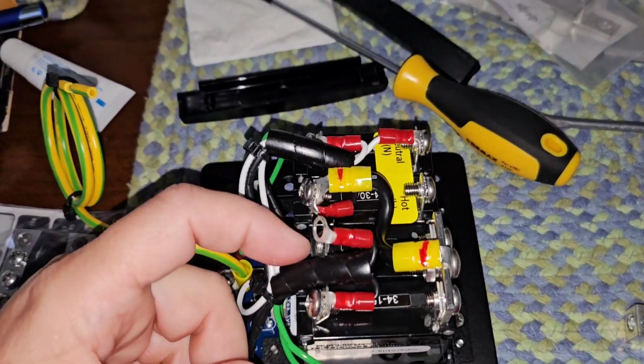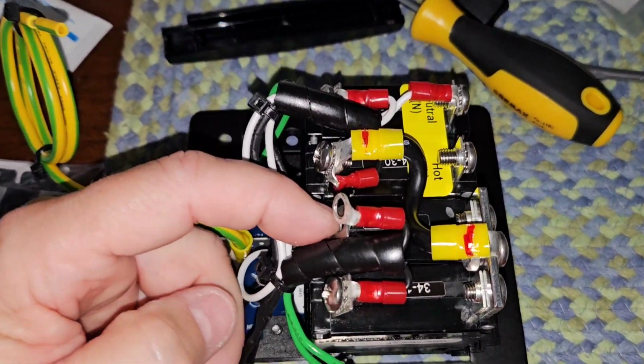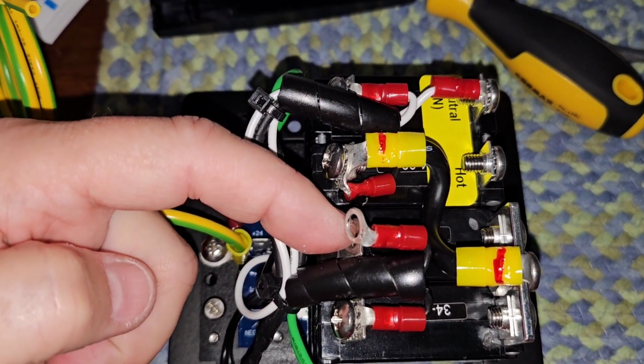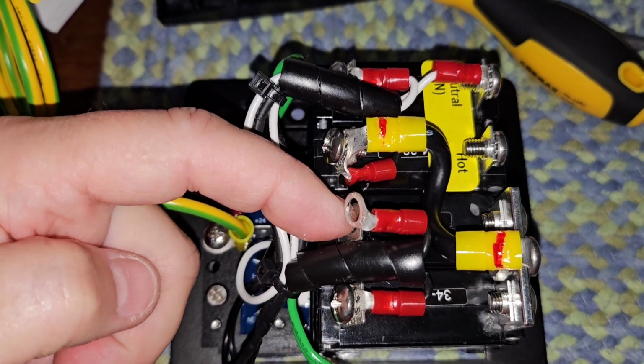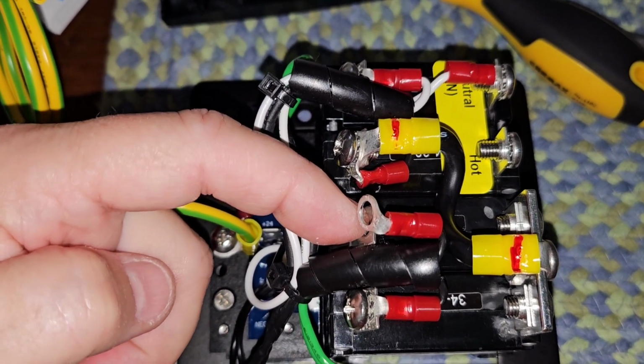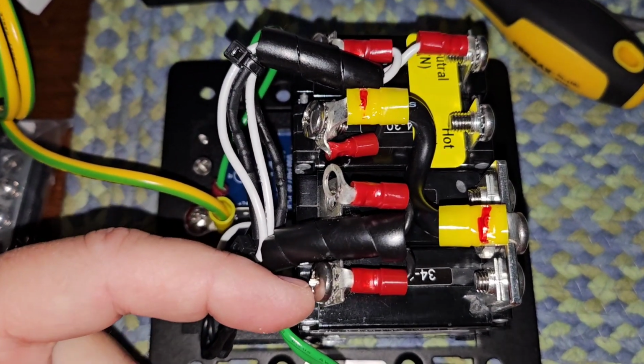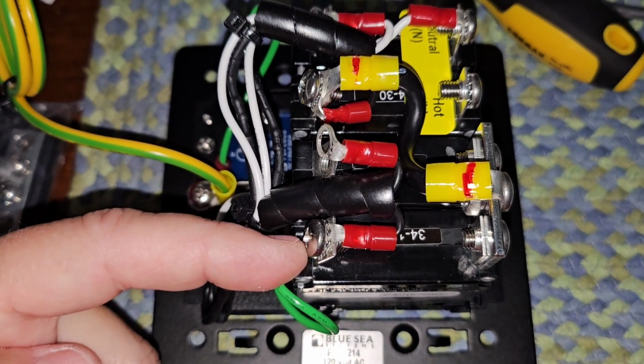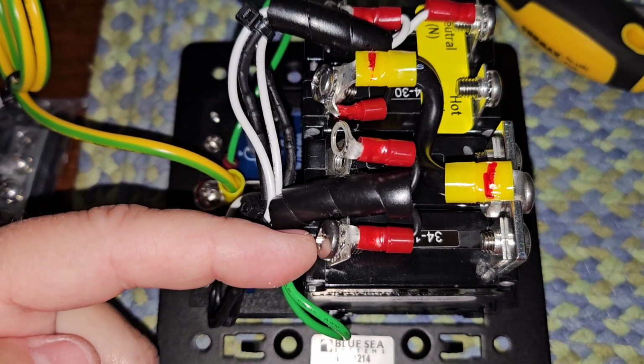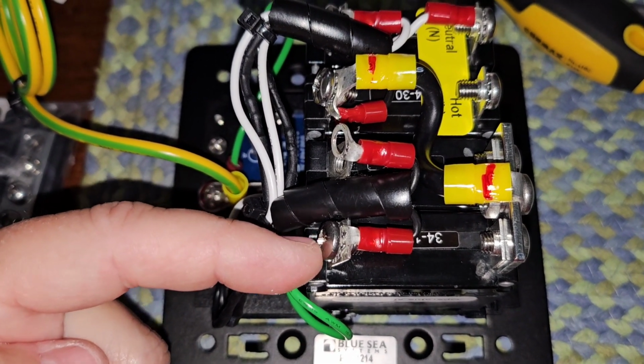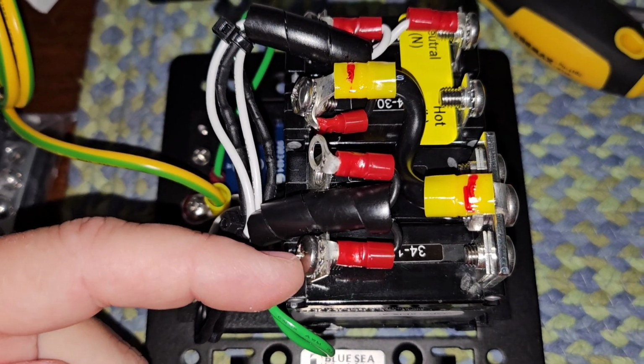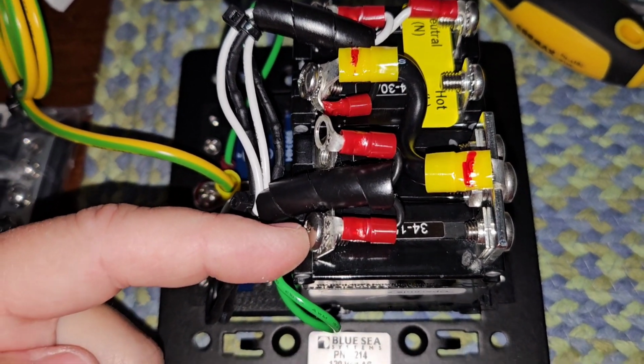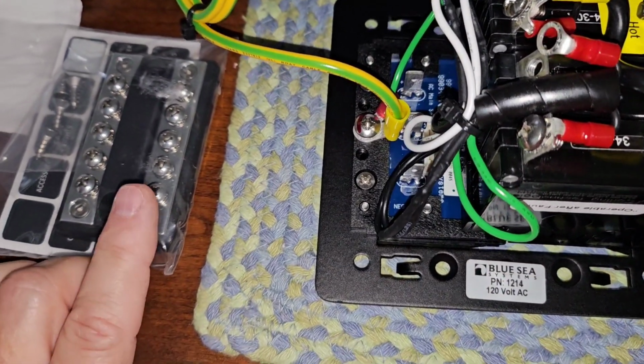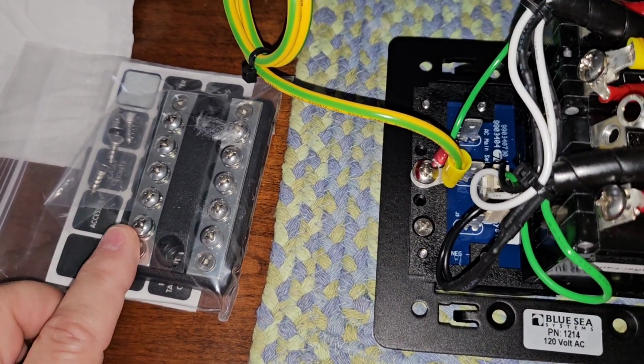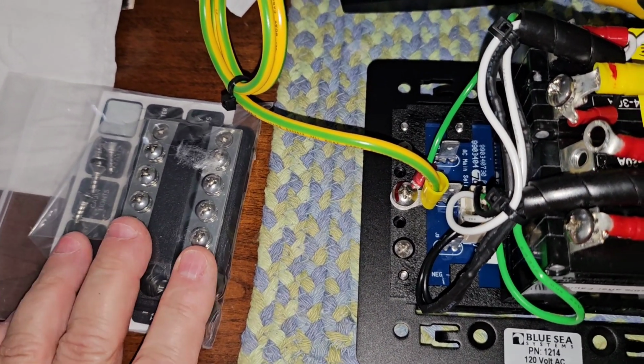My two circuit wires, white wire and bare ground wire, their load wires, the black wires, connect to the 20 amp circuit breaker for the air conditioner, and to the 15 amp circuit breaker for the TV and bed outlet. Their corresponding white neutrals and bare ground wires go on these ground bars.